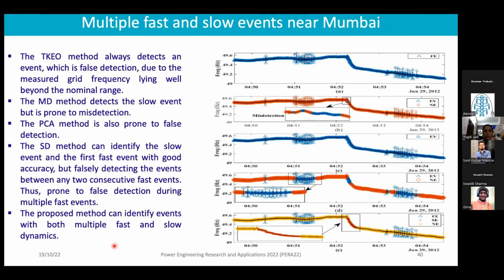Now there are multiple fast and slow events near Mumbai. Again, you can observe that the TKEO method is always detecting that an event is happening, but that's not so. We compared our observations with the reports uploaded on the corresponding RLDC centers, so we verified our results from there as well. Here no event is happening, but it keeps falsely identifying that an event is happening, because the measured grid frequency lies well beyond the nominal range.